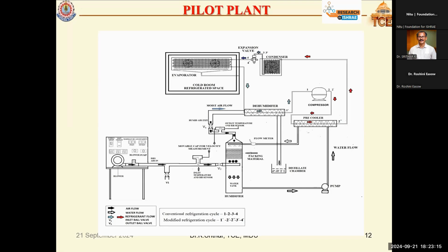This is called the humidifier chamber, where that hot water will be sprayed. At the same time, we have a blower to pump the air. The air goes from bottom to top. While it contacts this cellulose pad, better mixing takes place. Therefore, we are getting moist air. This moist air goes to this pipe flow, where we have another heat exchanger, placed in between the evaporator as well as the compressor. While the chilled refrigerant, which comes from the evaporator, contacts the moist air, the moisture from the air will be condensed. What we get is perfectly purified desalinated water.